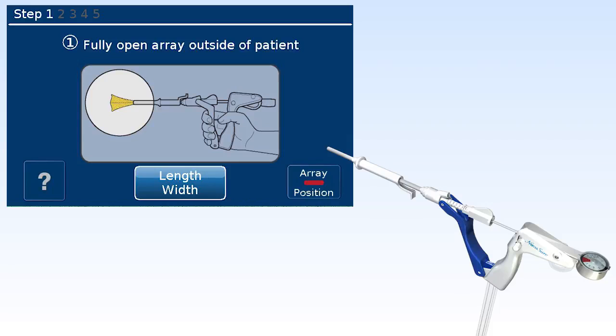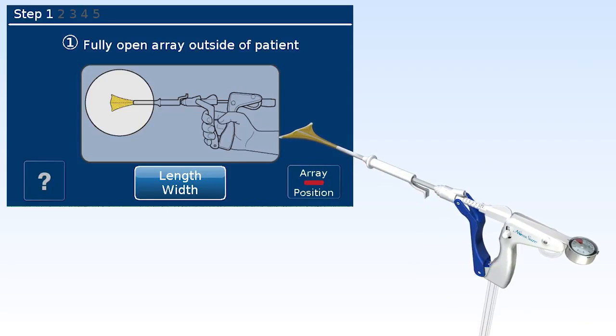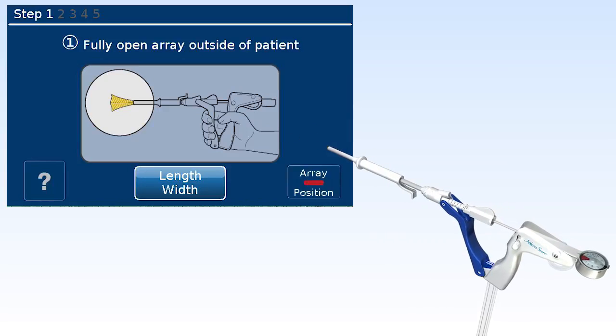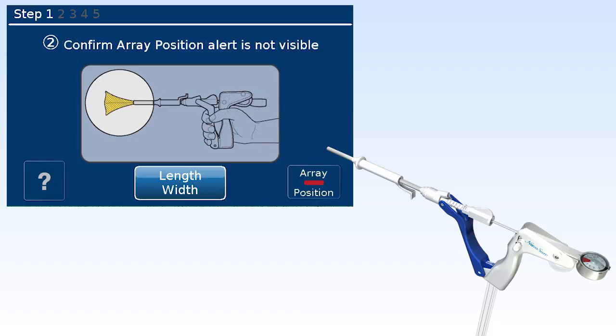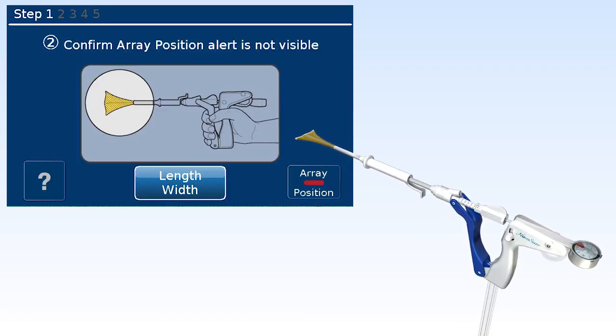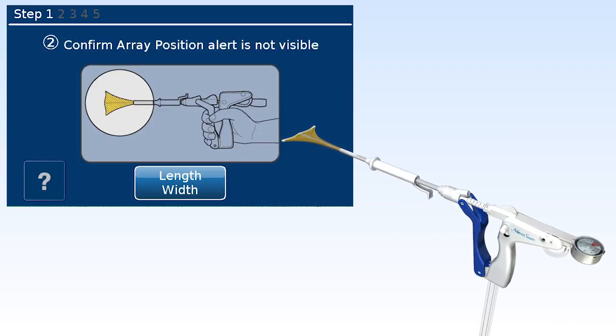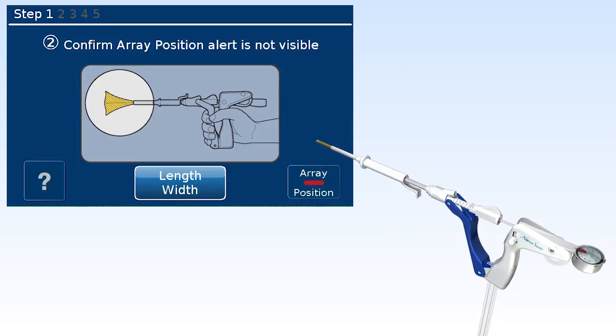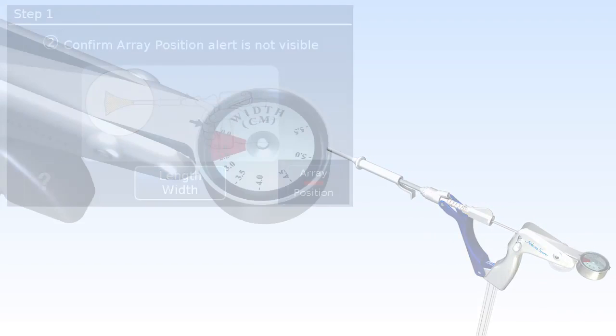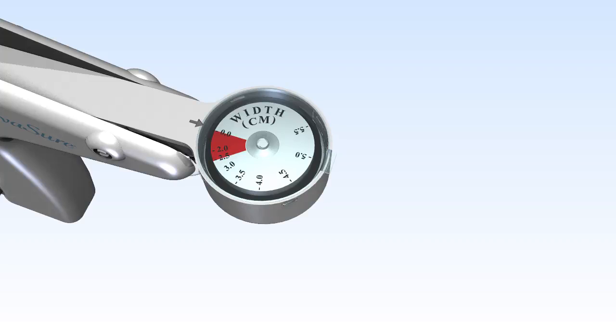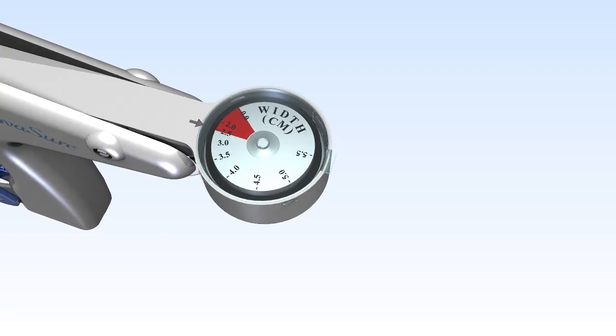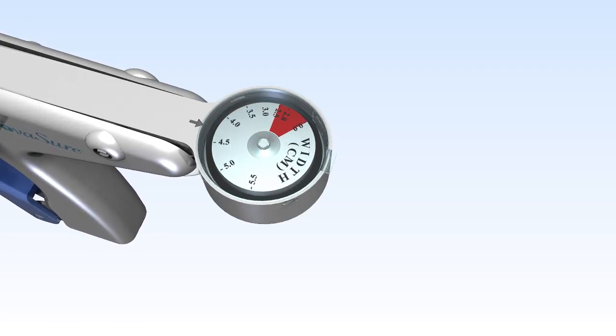Before setting the cavity length, check the NovaSure device outside of the patient by deploying the array, opening and closing the device. Ensure that the array position warning on the bottom right of the controller screen disappears when the device is deployed and reappears when the device is closed. Make sure the width measurement dial indicates a value greater than or equal to 4 centimeters when the device is deployed.